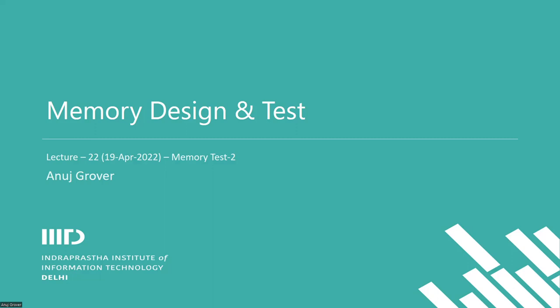So as a designer, I may want to leave design margins because it's a life critical device, going to be put in my heart sometime. I want to leave margins. I do not want it to fail. So I test it and ensure that it is verified. CAD verified at minus 40. There are margins.